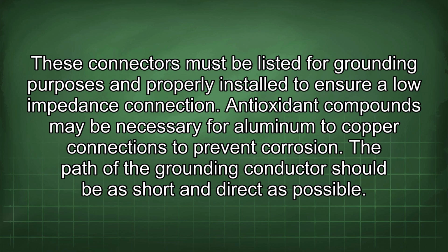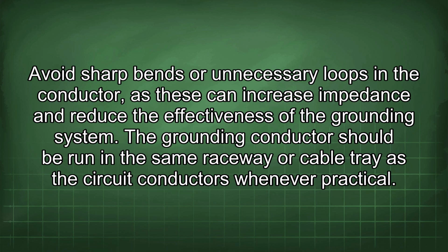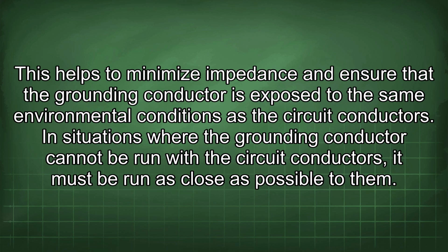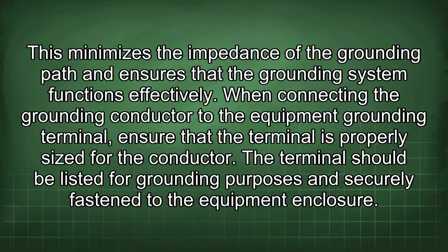The path of the grounding conductor should be as short and direct as possible. Avoid sharp bends or unnecessary loops in the conductor, as these can increase impedance and reduce the effectiveness of the grounding system. The grounding conductor should be run in the same raceway or cable tray as the circuit conductors whenever practical. This helps to minimize impedance and ensure that the grounding conductor is exposed to the same environmental conditions as the circuit conductors. In situations where the grounding conductor cannot be run with the circuit conductors, it must be run as close as possible to them. This minimizes the impedance of the grounding path and ensures that the grounding system functions effectively.